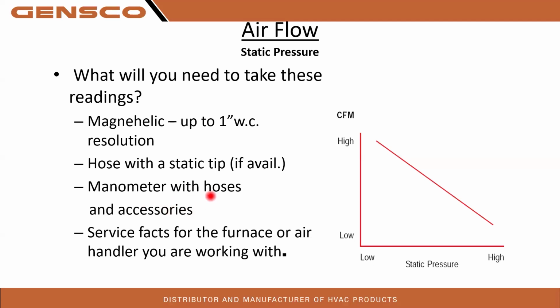I'll show you a picture of the Magnehelic and a picture of the digital version. Service facts for the furnace or air handler. You must have service facts. And I tell everybody, please read through those service facts and the install manual when you have free time. Know what's in there. And that's the only way we can for sure dial in our airflow. Right? So here's the graph.